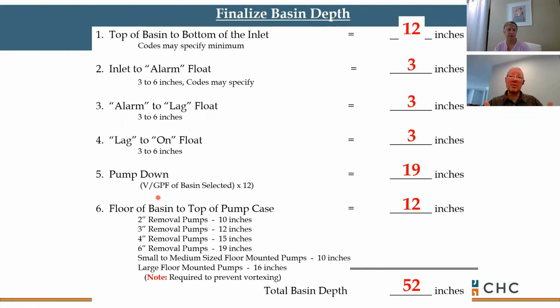So we can put all this into a quick sizing selection summary. If our invert is 12 inches below grade, and my high water alarm is going to be 3 inches below that, and my lag pump control is 3 inches below that... sorry, 3 inches from my invert to my high water alarm. I've got an alarm to lag float to 3 inches, and then my lag to lead pump is 3 inches. And I need 19 inches of usable water within my basin, and my minimum water level is 12 inches. All that totals up to a basin of 42-inch diameter by about 52 inches deep.